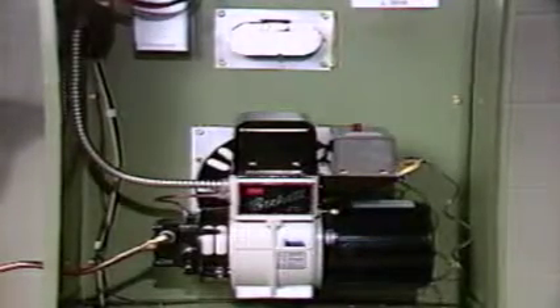The third condition is the failure of the ignition arc. Let's listen for it. If you can't easily hear the ignition arc buzz, raise the transformer slightly until you can see the arc between the electrodes and the transformer output. A flame mirror may be necessary to check for arcing at the electrode gap. If the homeowner mentioned the odor of fuel oil or fumes, the ignition may be delaying, producing puffbacks, which create fumes. If the spark is inadequate or fails to get established, the burner will lock out on safety.